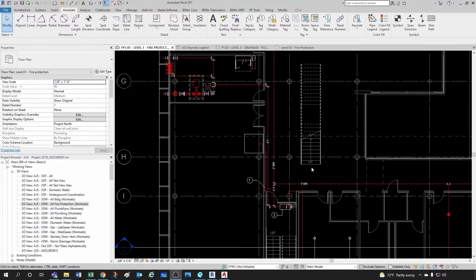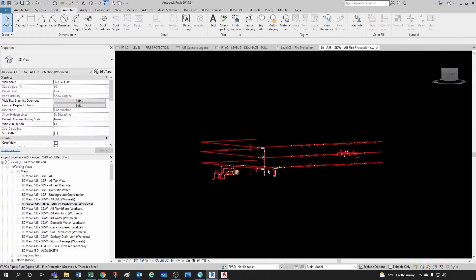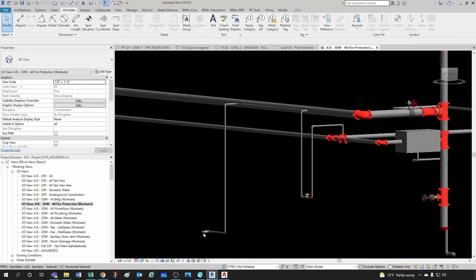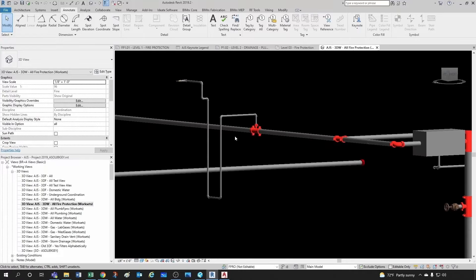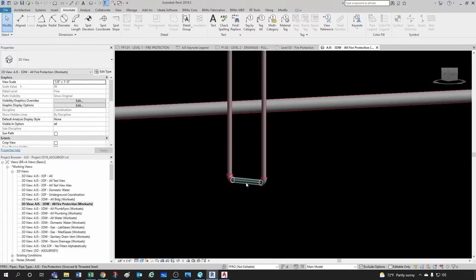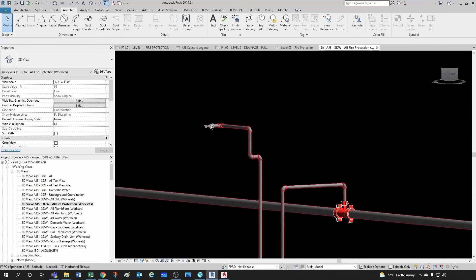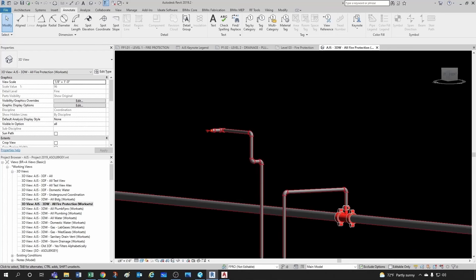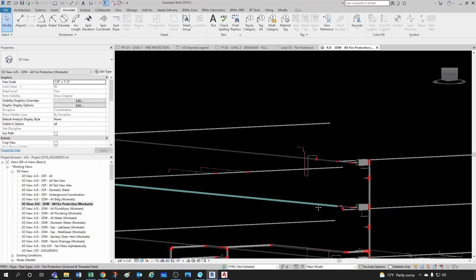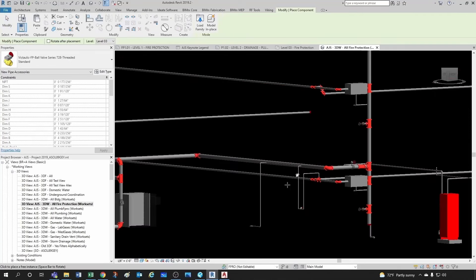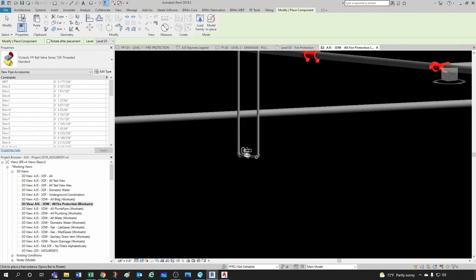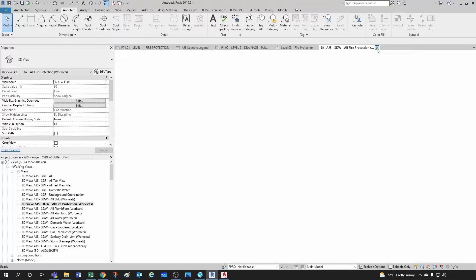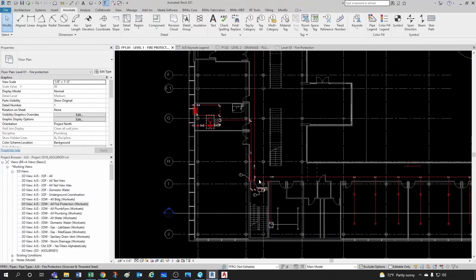One last thing I want to show you: if I go to my 3D fire protection riser, you'll see I added one of these valves with a bottom-of-pit sprinkler here. On the top floor I'm going to add another valve that controls a sidewall sprinkler at the top of the elevator shaft. I'm going to create similar, get this out of the way, and go back to my floor plan for level one. Notice that I have one tag for this.